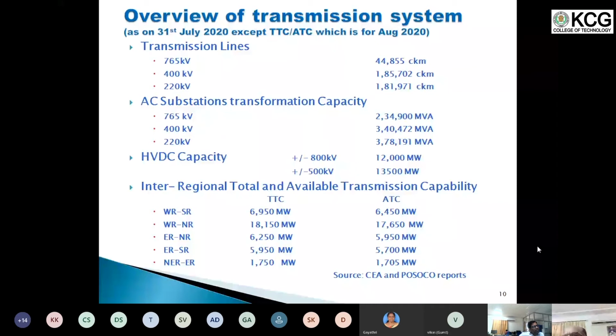I have used two terms here: TTC, the total transmission capability, and ATC, the available transmission capability. The difference between the two is that for grid operation, you keep some margin depending on your assessment of the deviations in flows which can happen. So for WR-SR, you keep a margin of 500 megawatt; for some regions, 250 megawatt, and so on.